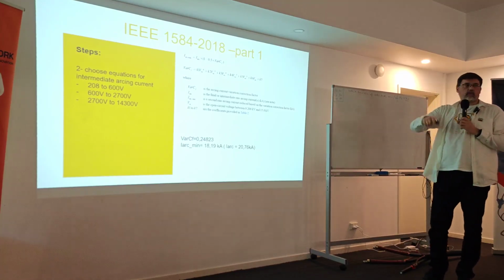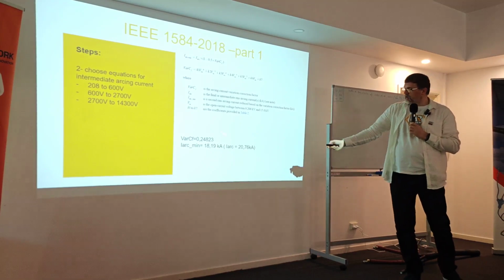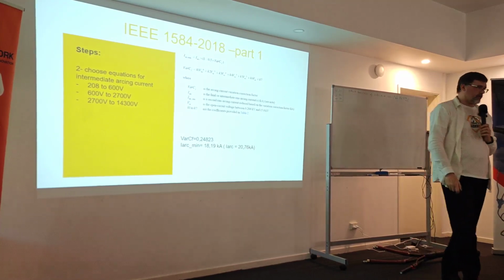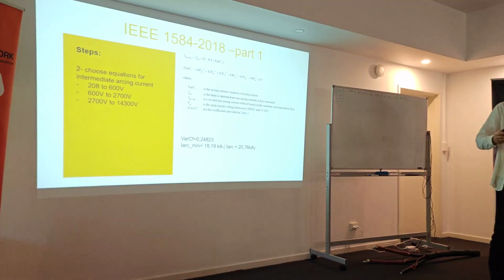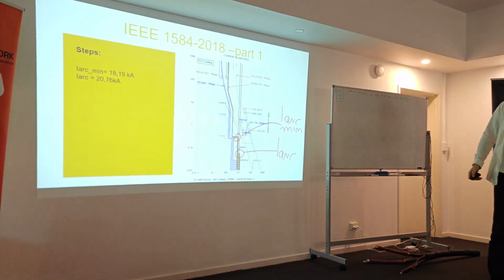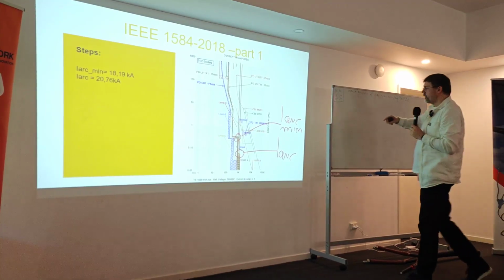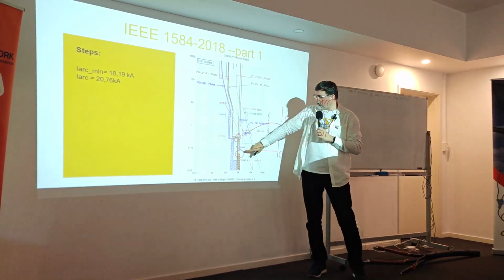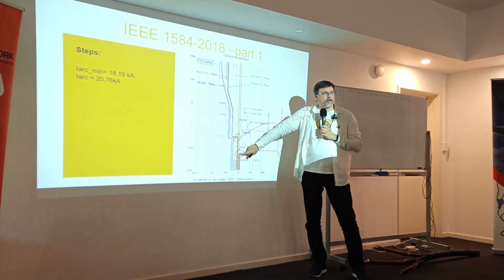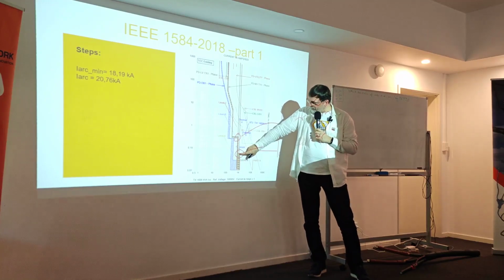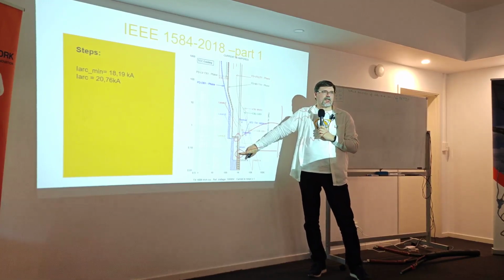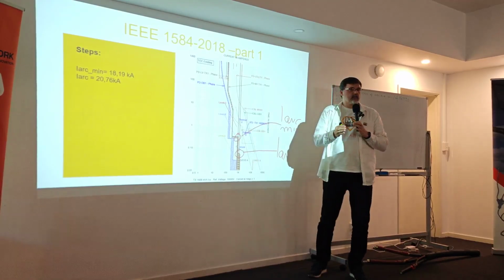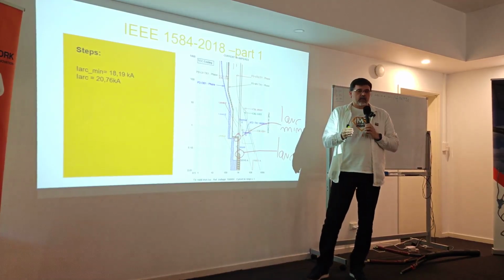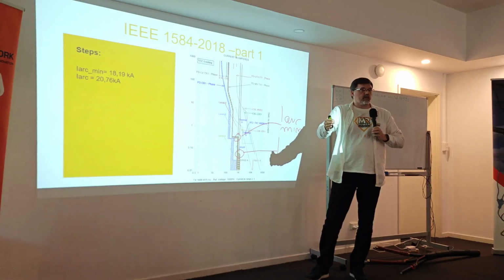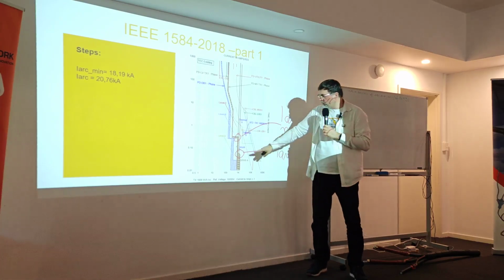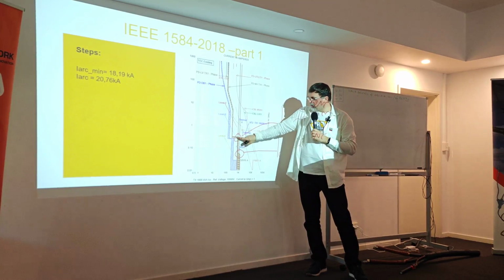If this is not the problem, we come back to the other one. So we calculated this was 18.9 comparing to 20.7, so 2 kiloamps less almost. And then we go and check. And my idea was to show you like this. So this is the typical situation that your arc current, the normal one you calculate, is somewhere here, which you can see is very close. It's not that you just make, at least you make a small mistake in the calculation. It's not 20 millimeters, but 25 or something. Then your current will drop and then you are somewhere here.